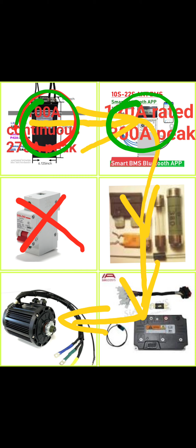The BMS should be rated a tiny bit higher than what the battery is capable of putting out. The reason is because we want to avoid hitting the limits of the BMS all the time, because it can trip spontaneously.